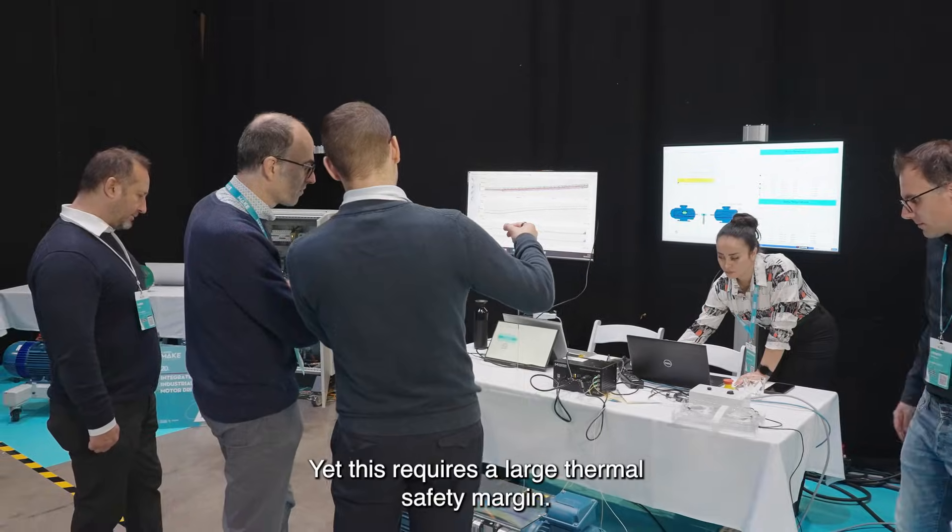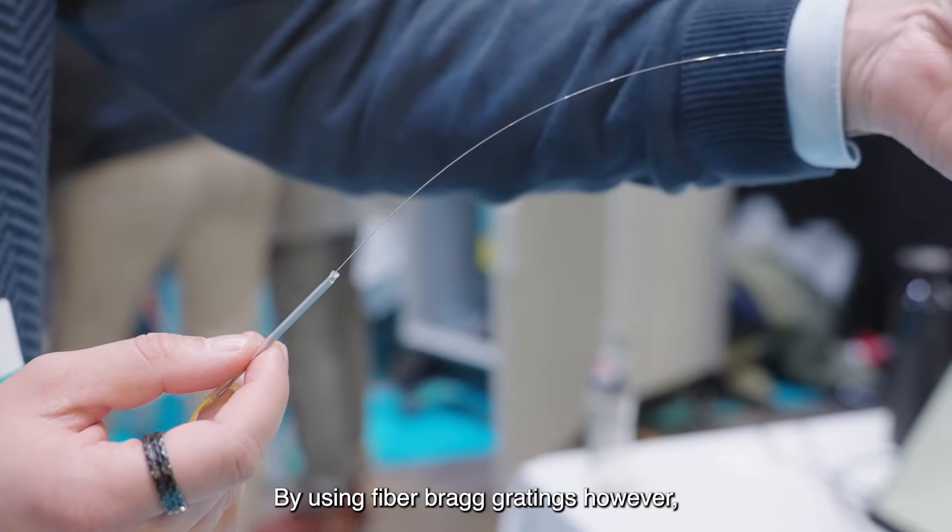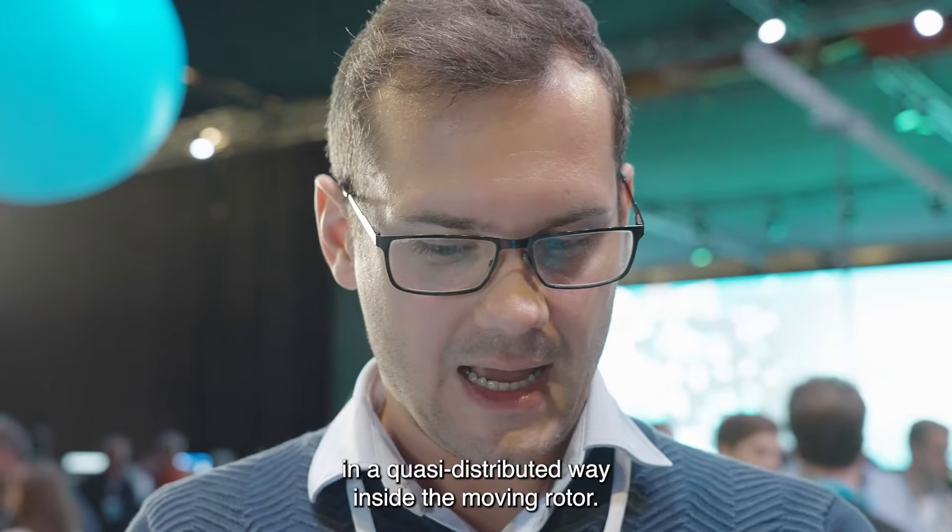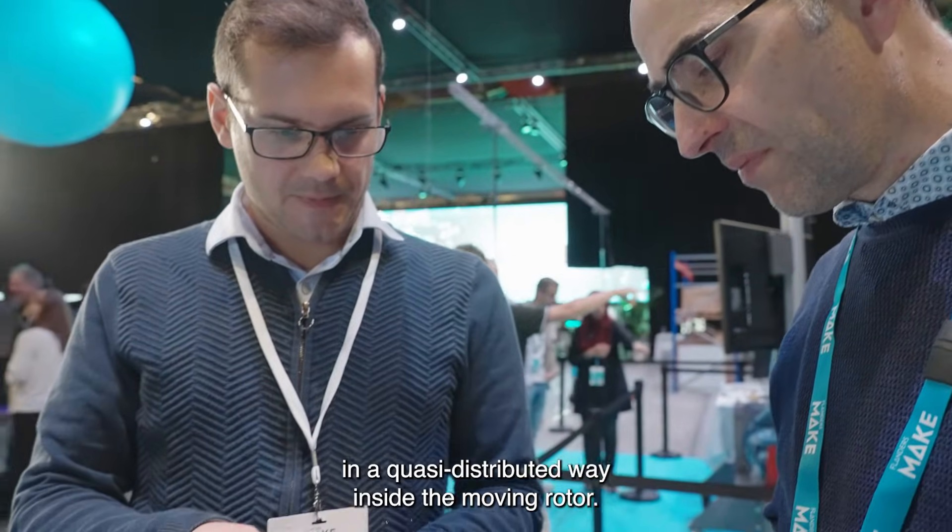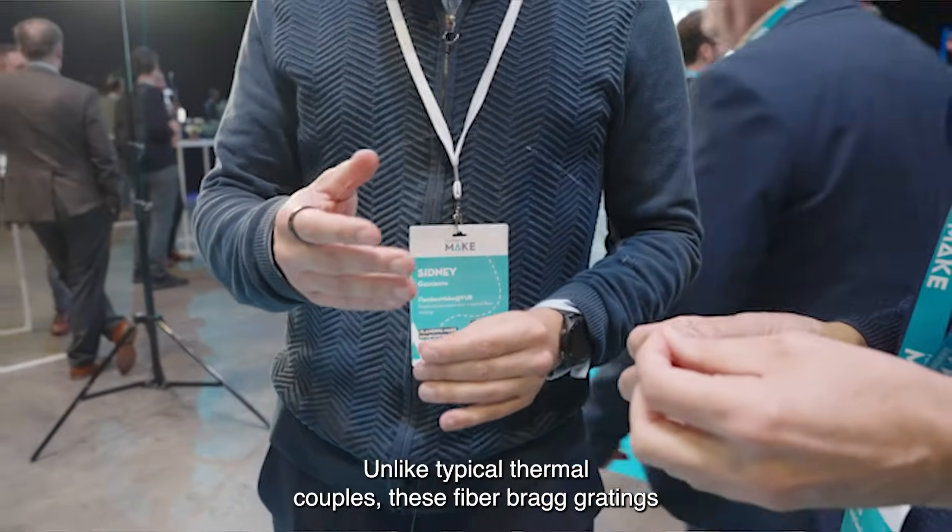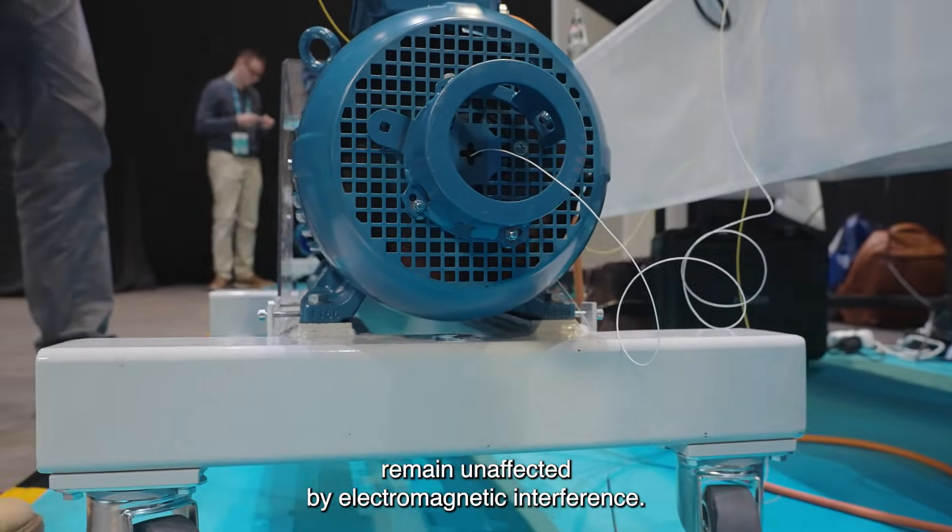Yet this requires a large thermal safety margin. By using Fiber Bragg Gratings, however, we are able to accurately measure temperatures in a quasi-distributed way inside the moving rotor. Unlike typical thermocouples, these Fiber Bragg Gratings remain unaffected by electromagnetic interference.